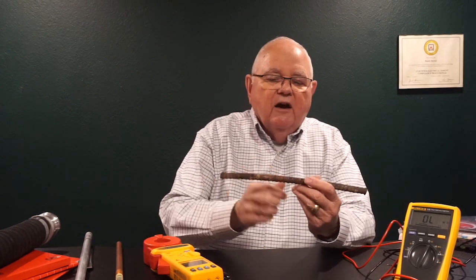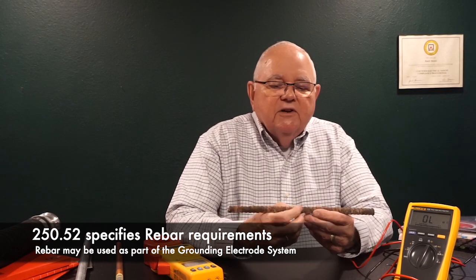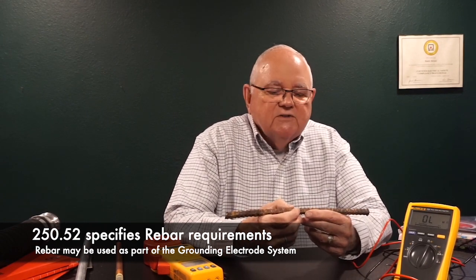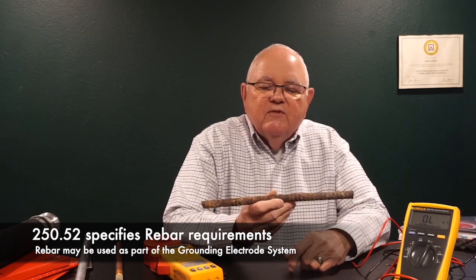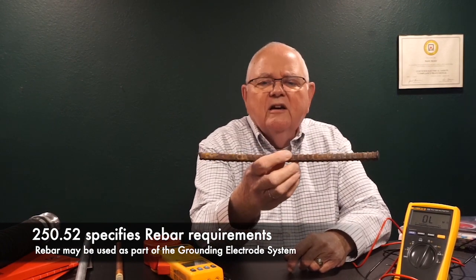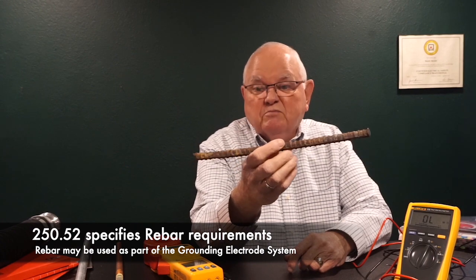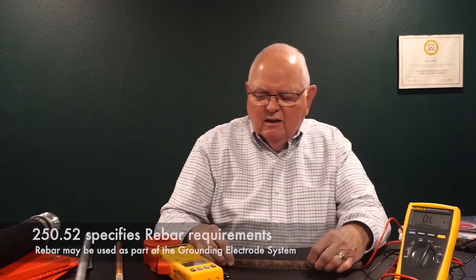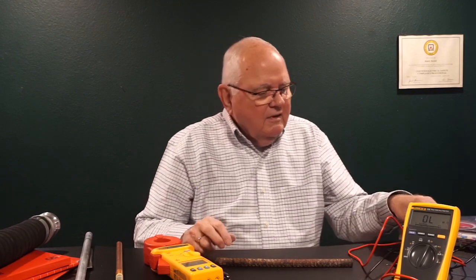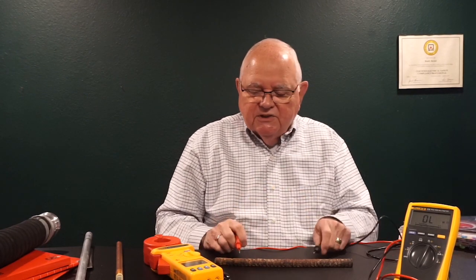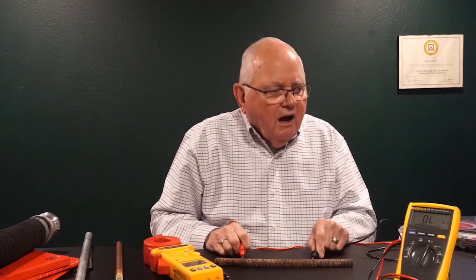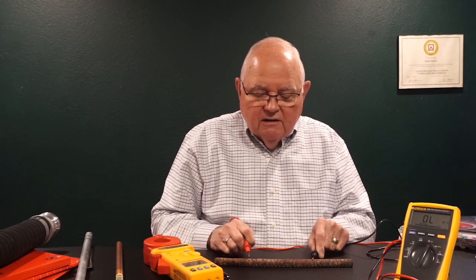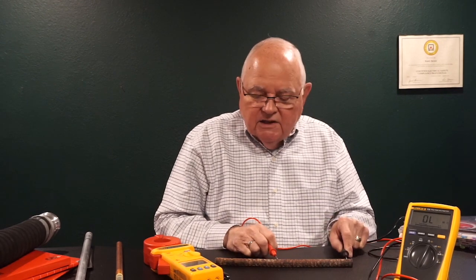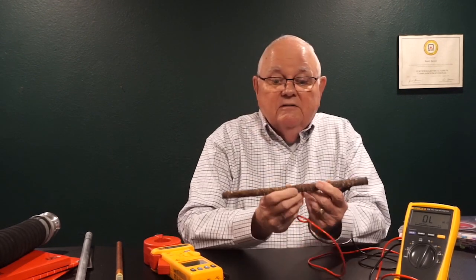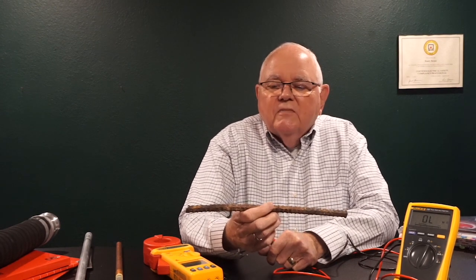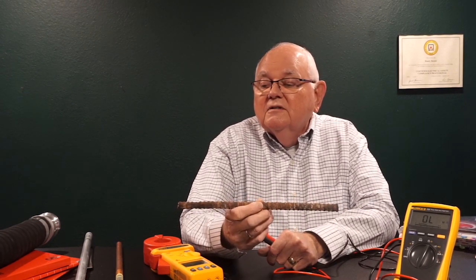Now, we use a lot of rebar, don't we? Rebar, that we can use certain rebar, according to the National Electrical Code, for grounding and bonding. So this must be very conductive then. So I've got an old piece of rebar here, and it's been outside, it's pretty rusty and so forth. So if I take this rebar and read the resistance across that rebar, I get OL on my meter, open circuit. I'm getting infinity. Holy man, that's not good. Holy buckets, man. This iron rust on there is a good insulator.